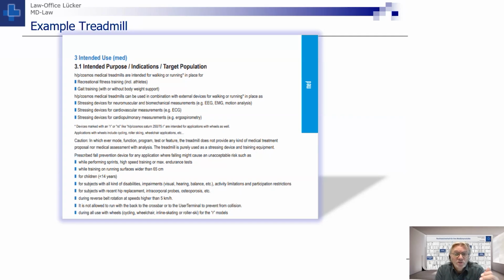Gait training, for example, or a stressing device for neuromuscular, biomechanical measurements, for cardiovascular measurements, etc. So there's a clear medical specific intended purpose. And in each case where you find this information in the instruction for use or in the declaration of a treadmill, that treadmill has medicinal or medical intended purposes. It's a medical device, regardless whether classified or categorized by the manufacturer as machine or not, it is a medical device, and as a distributor, you can't make it available on the market.